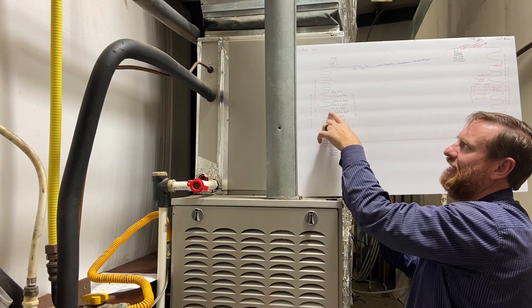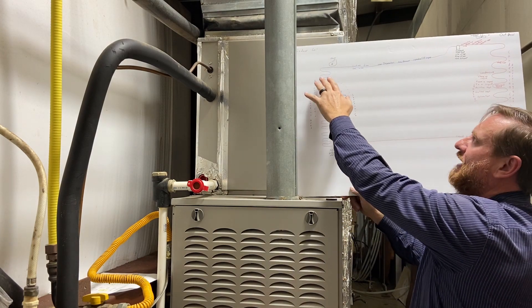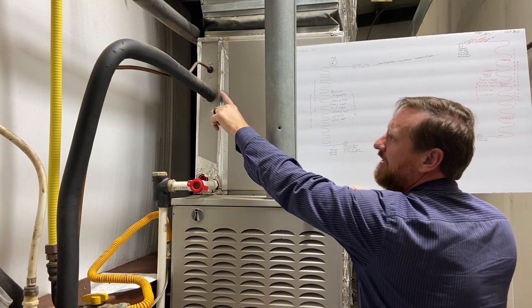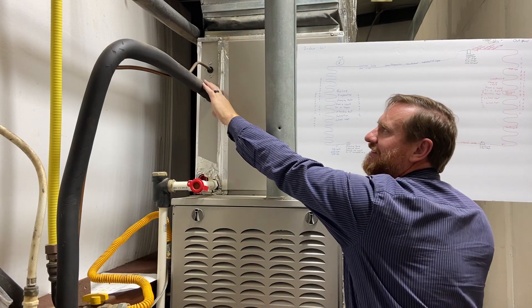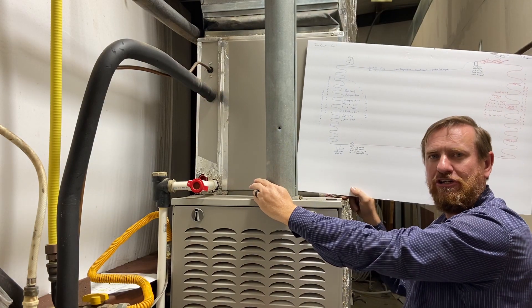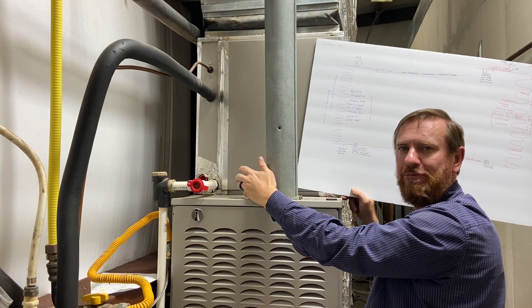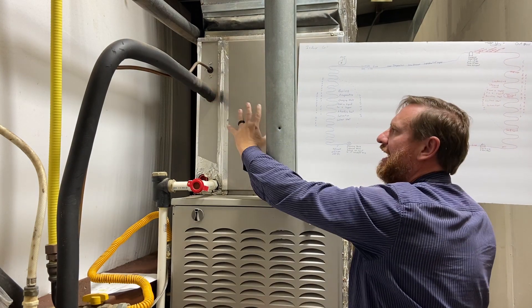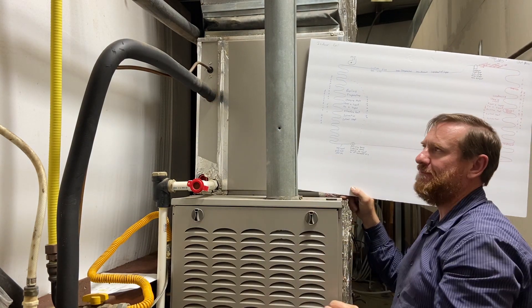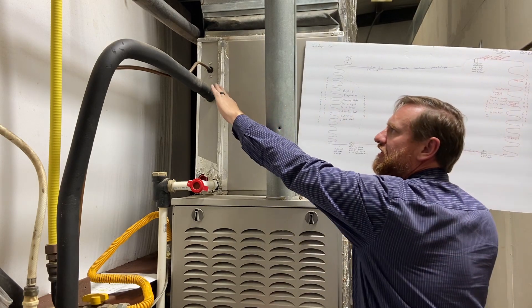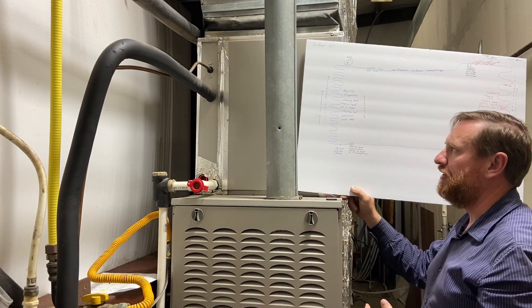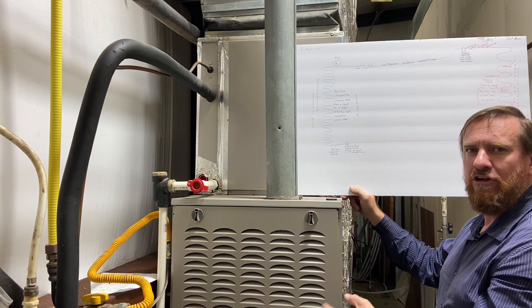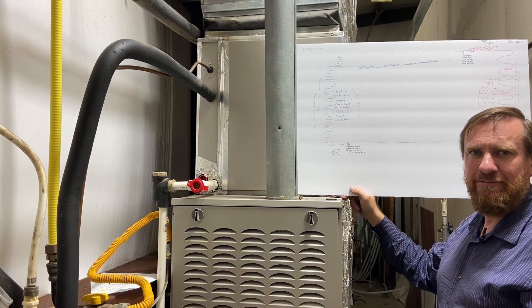After we change it all from a liquid to a vapor, we have vapor coming all the way back to the compressor. Here we see this suction line — it's insulated because it's low temperature, low pressure, and it's still trying to absorb heat. We insulate it because we only want to absorb heat at the evaporator coil. When you touch this line it's going to feel low temperature. This is where that boiling point is actually happening. When we get the pressure, we convert it to a saturated temperature.